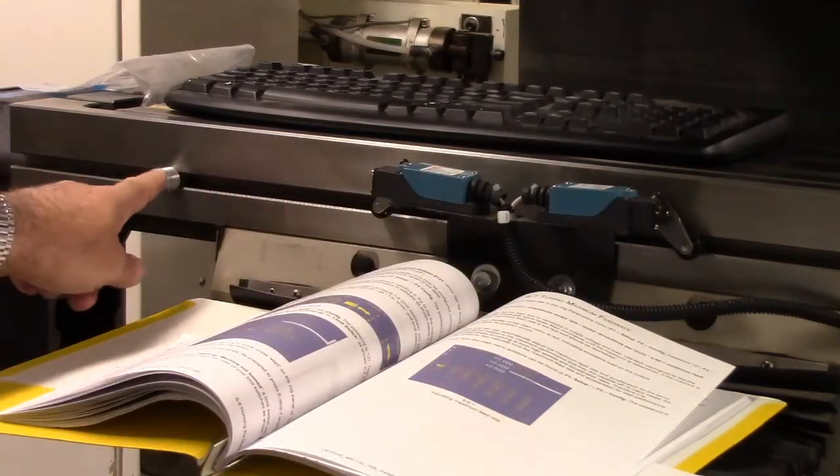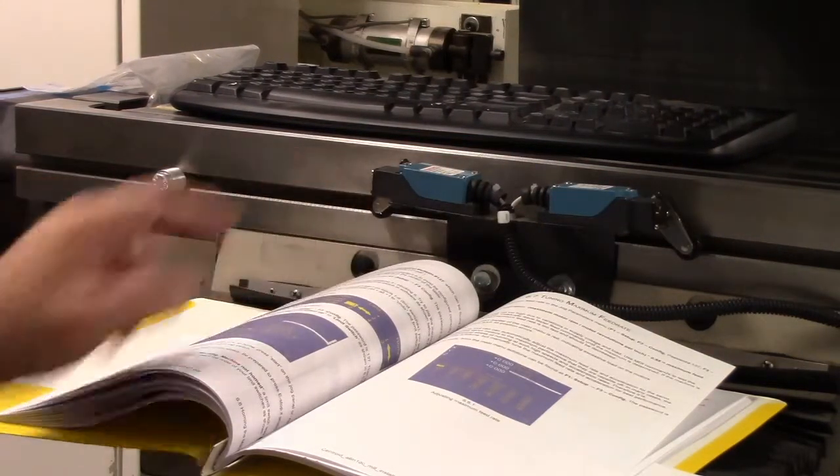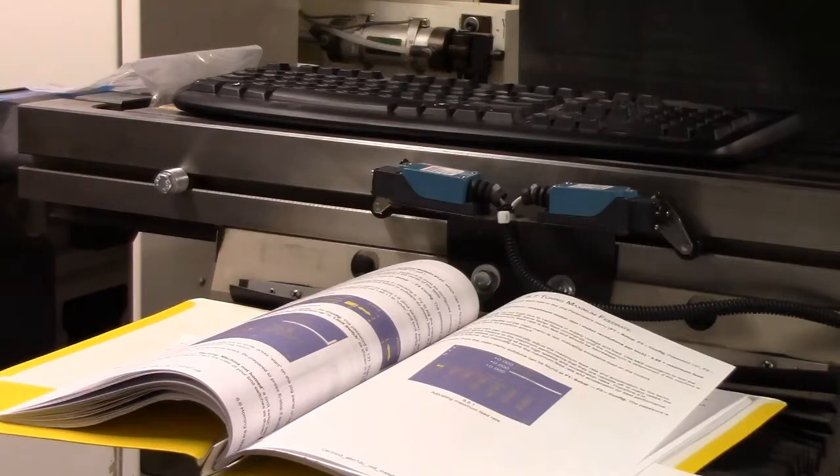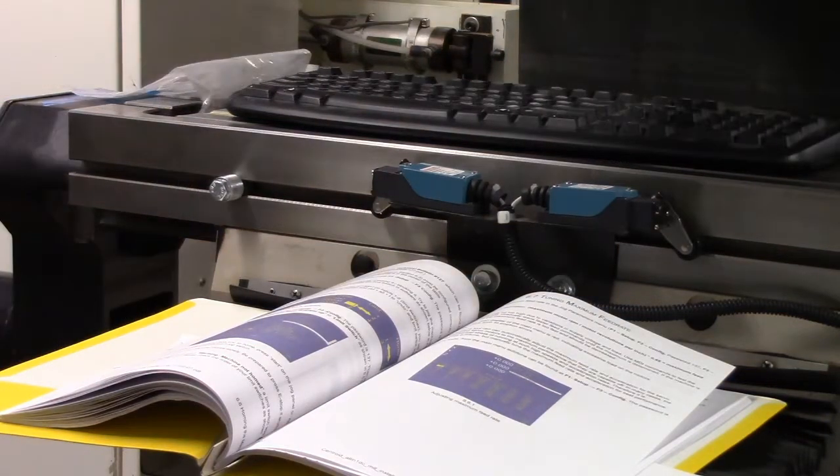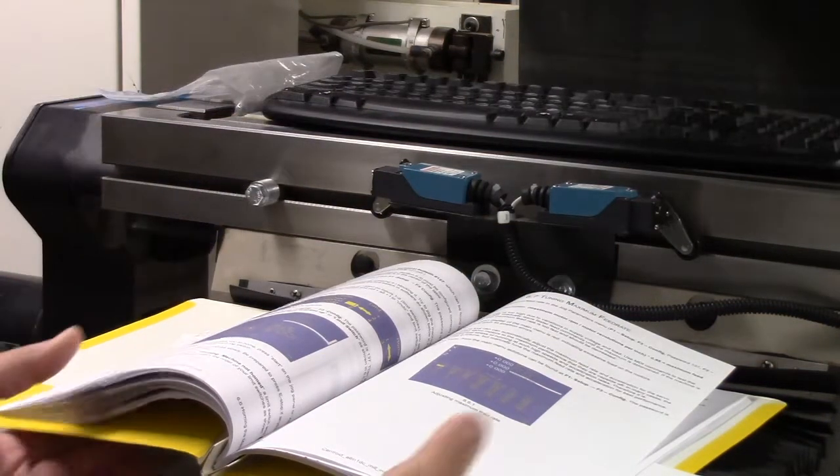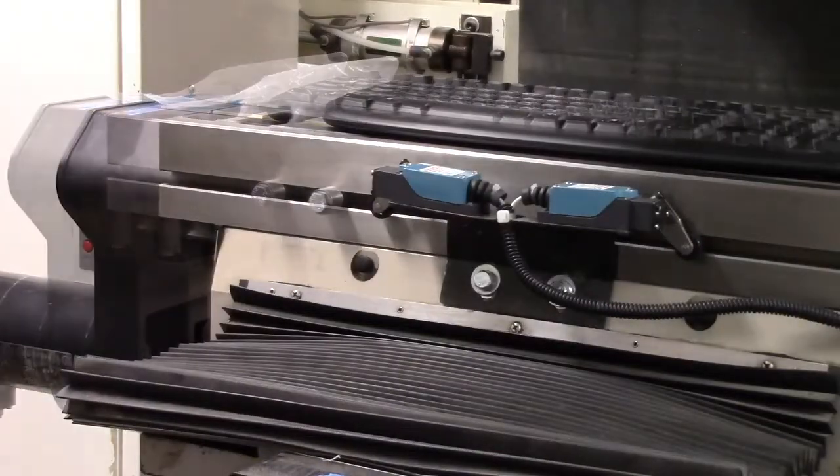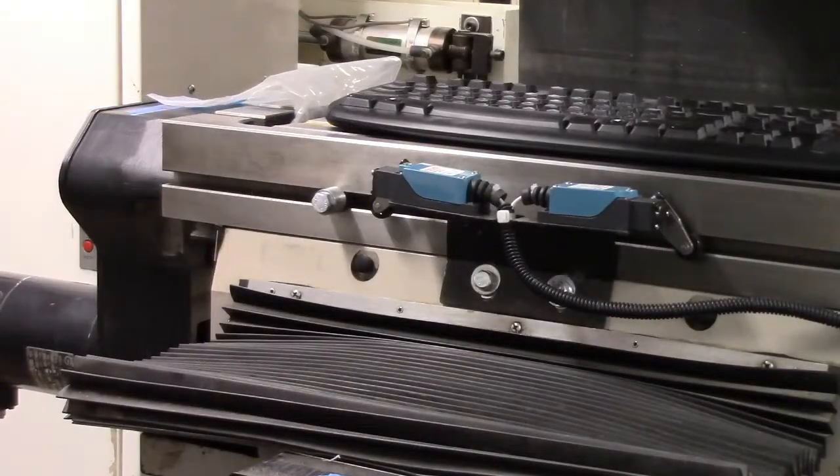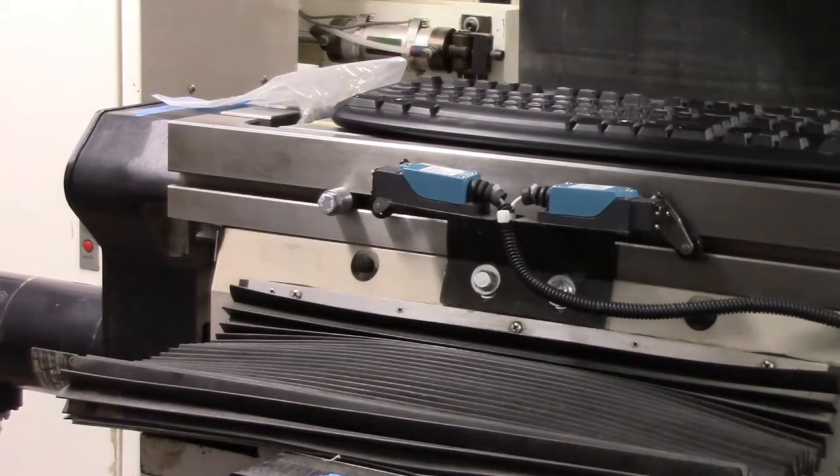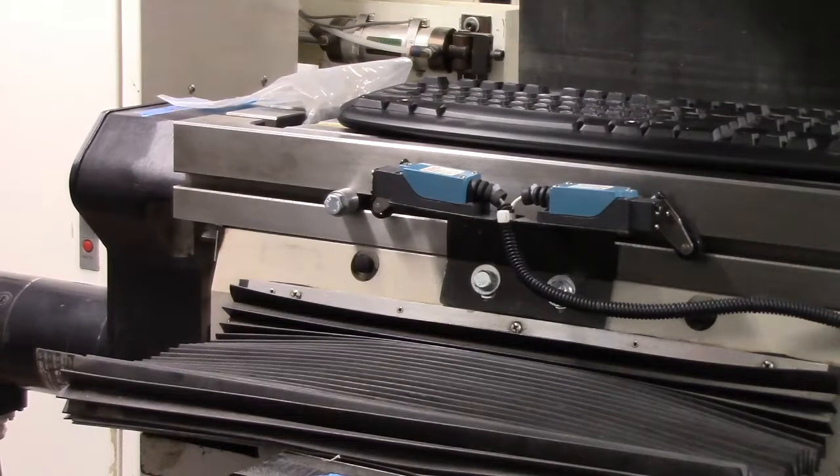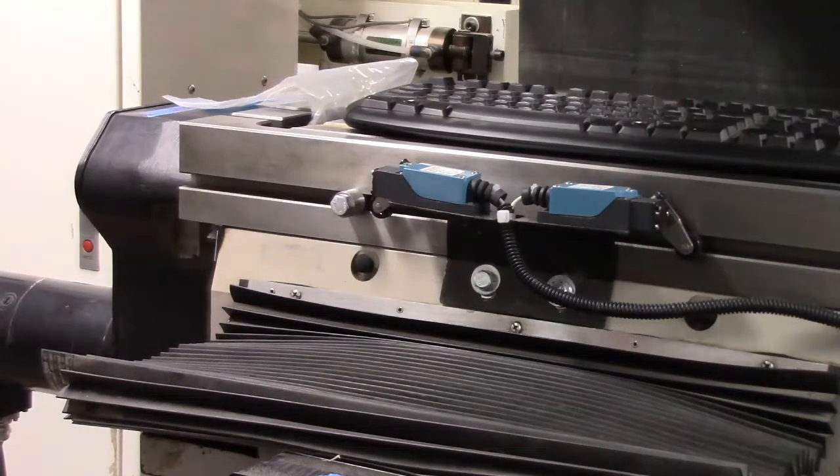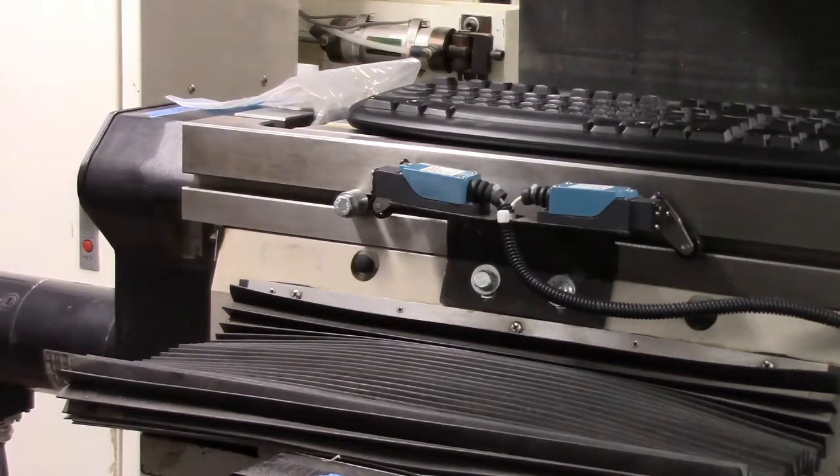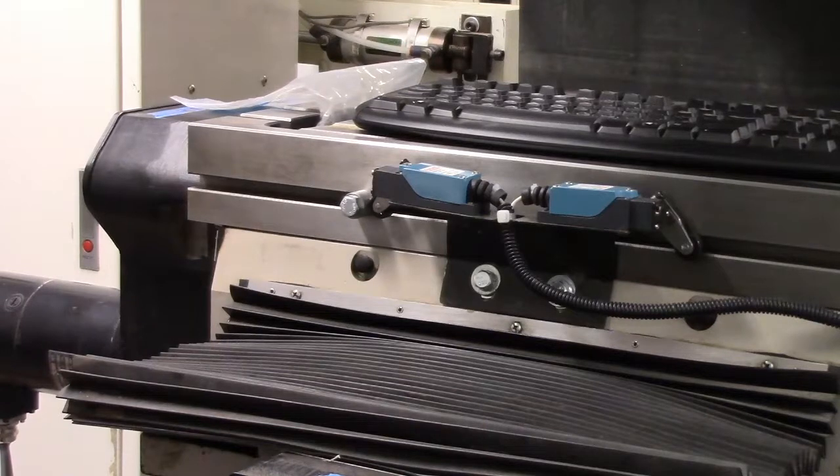You see that tripper is coming in towards the limit switch, getting closer. This is why it's so important to check your switches manually before doing this. So I'm about ready to dive on the E-stop if it doesn't work.